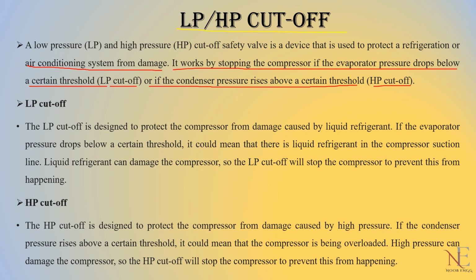Now the LP basically works for compressors, and the HP works for condensers. So what is an LP cutoff system? An LP cutoff is designed to protect the compressor from damage by liquid refrigerant. Now, how does it protect it? As the pressure drops below a certain threshold point, it could mean that there is liquid refrigerant in the compressor suction line.